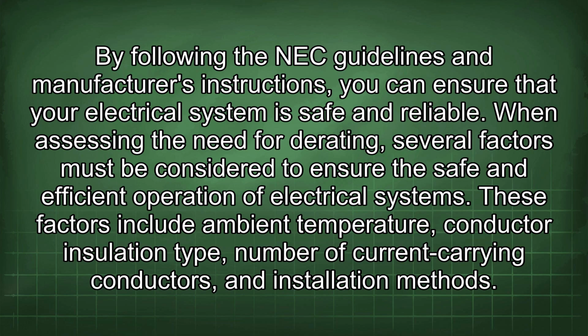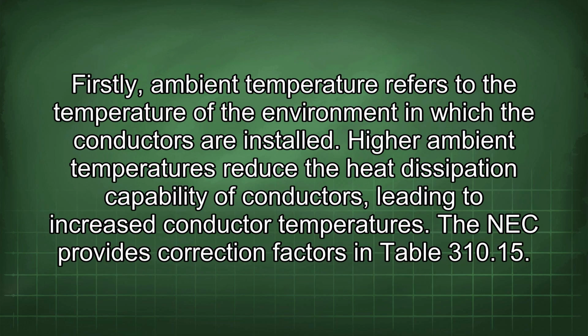When assessing the need for derating, several factors must be considered to ensure the safe and efficient operation of electrical systems. These factors include ambient temperature, conductor insulation type, number of current carrying conductors, and installation methods. Firstly, ambient temperature refers to the temperature of the environment in which the conductors are installed. Higher ambient temperatures reduce the heat dissipation capability of conductors, leading to increased conductor temperatures.